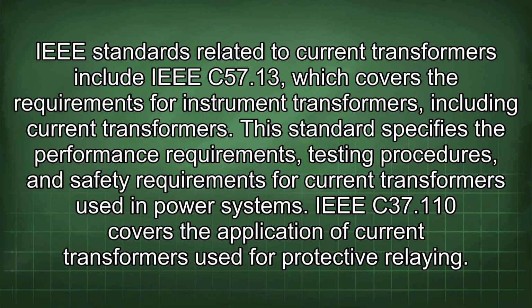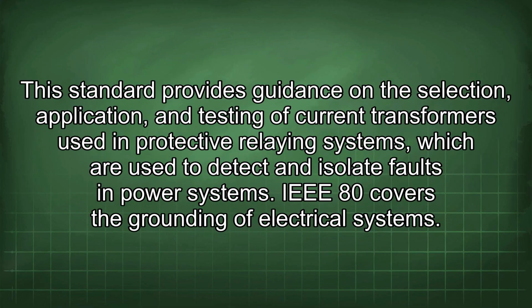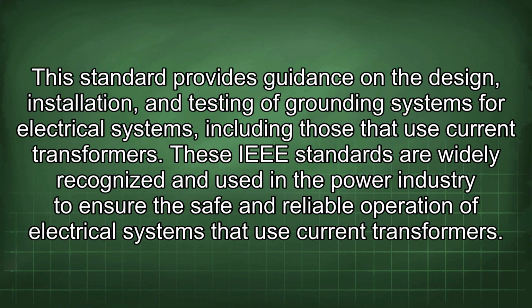IEEE C37.110 covers the application of current transformers used for protective relaying. This standard provides guidance on the selection, application, and testing of current transformers used in protective relaying systems, which are used to detect and isolate faults in power systems. IEEE 80 covers the grounding of electrical systems. This standard provides guidance on the design, installation, and testing of grounding systems for electrical systems, including those that use current transformers. These IEEE standards are widely recognized and used in the power industry to ensure the safe and reliable operation of electrical systems that use current transformers.